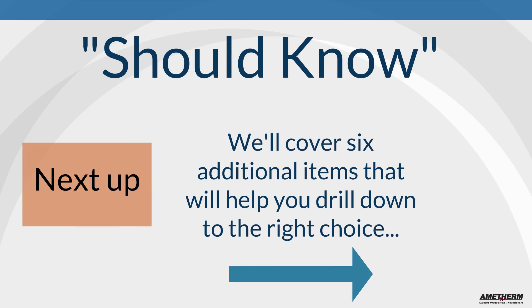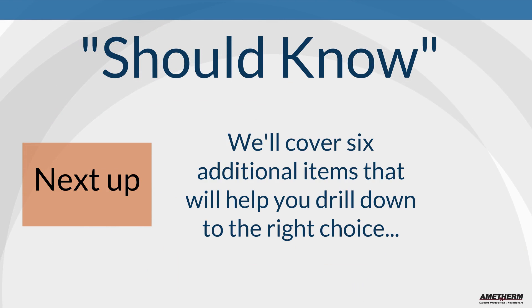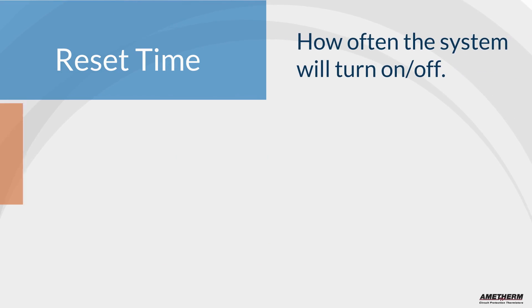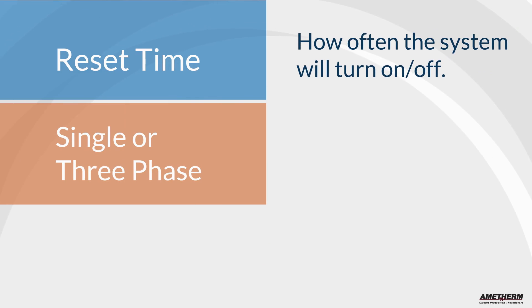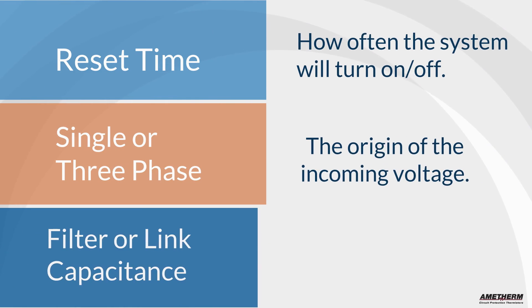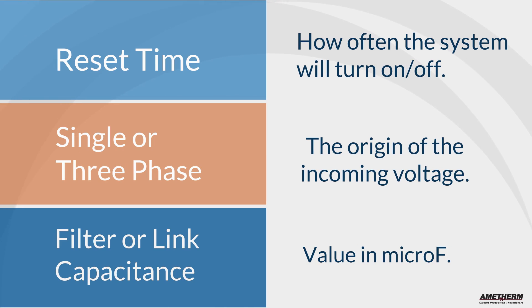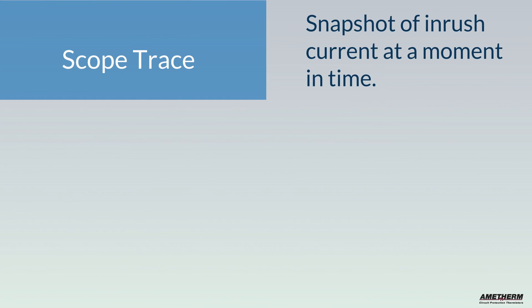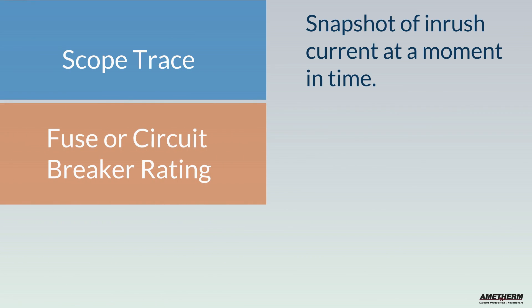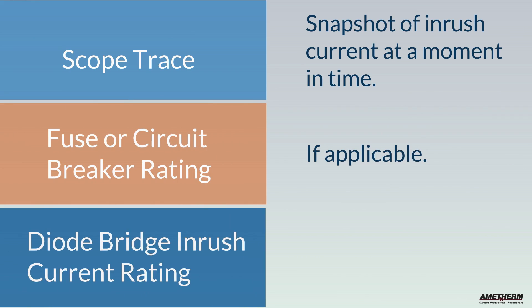Next, we'll cover six additional items that will help you drill down to the right choice: reset time — how often the system turns on or off in a specified time frame; single or three phase — the origin of the incoming voltage; filter or link capacitance value in microfarads — this quantifies the magnitude of the capacitance; scope trace — a snapshot of inrush current at a moment in time; fuse or circuit breaker rating if applicable; and diode bridge inrush current rating if applicable.